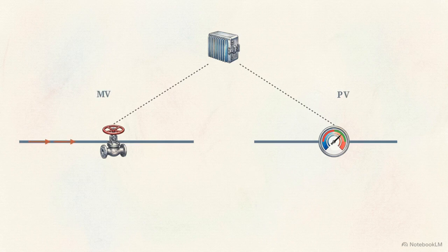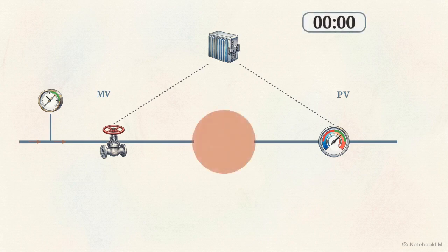It watches the product temperature, our primary process variable, or PV, and adjusts a steam supply valve, the manipulated variable, to keep that temperature on target. But watch what happens when a process disturbance hits. If the main plant steam header pressure suddenly drops, the heat energy flowing into our exchanger plummets. And yet the steam valve doesn't move a millimeter. The controller doesn't know the steam pressure dropped.